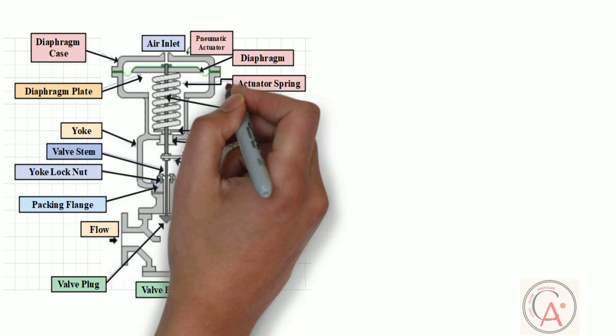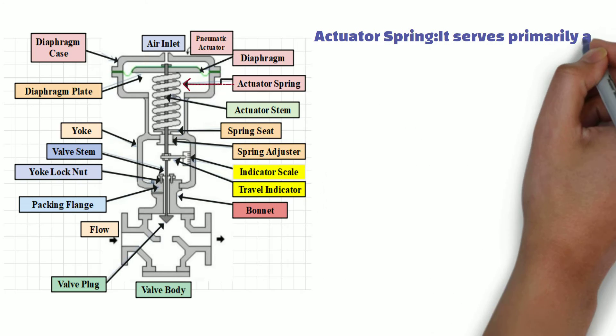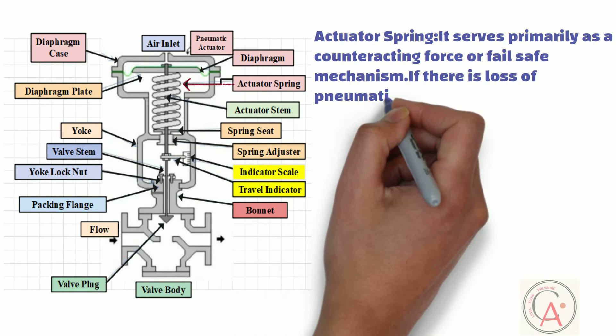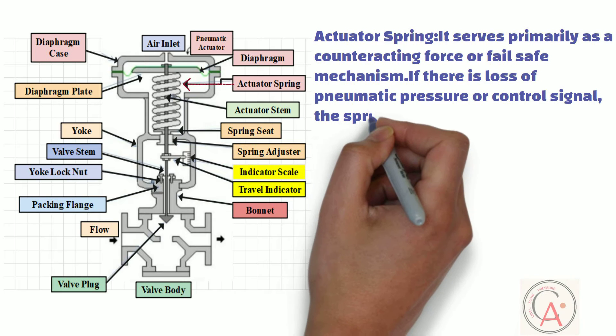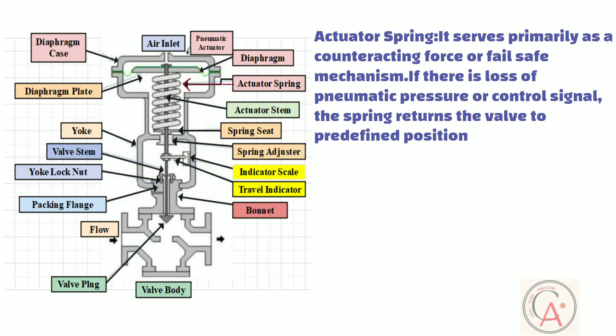Another important part is the actuator spring. The spring within the actuator serves primarily as a counteracting force or fail-safe mechanism. If there is a loss of pneumatic pressure or control signal, the spring returns the valve to a predefined position, usually fully open, fully closed, or a specified intermediate position.